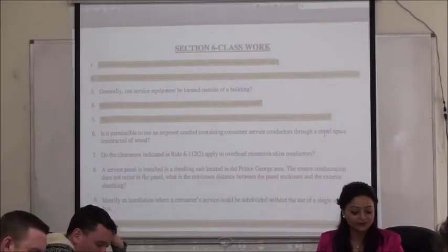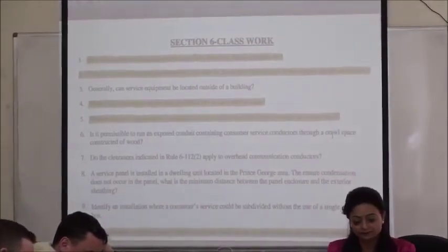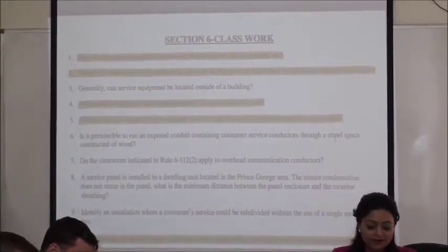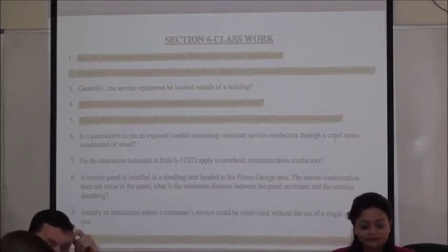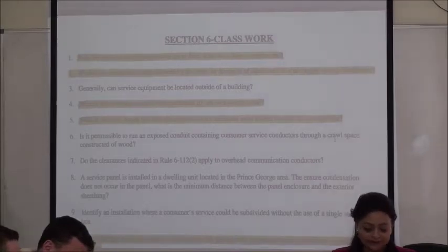Question number 2 for Mary: what is the maximum height allowed by code for the service wires? Nine meters. Next question for you: minimum conduit size for a service mast? Rule 6-112, sub-rule 3: 63 millimeters, which is two and a half inches. Very good.